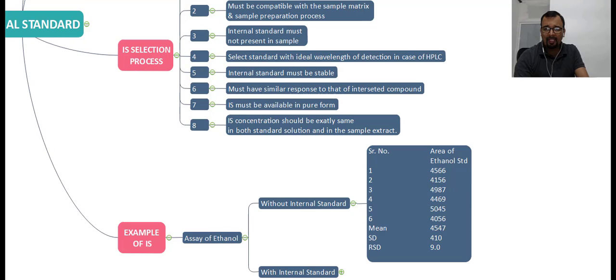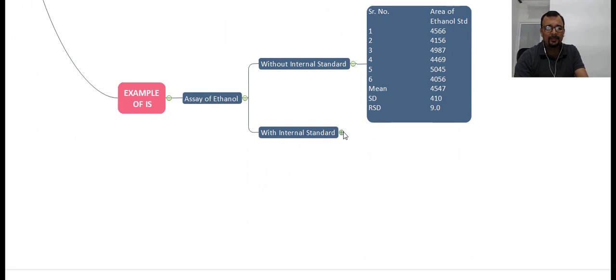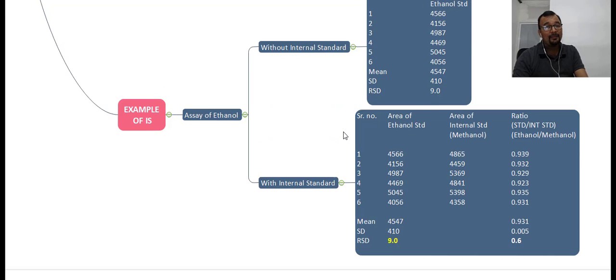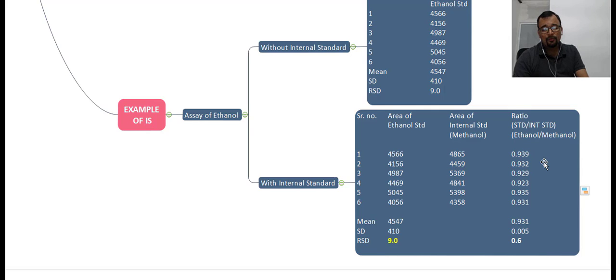Now, in a similar experiment but using an internal standard, methanol is added as the internal standard. Here are the peak responses of the methanol. As part of the process, you calculate the ratio of the ethanol area to the methanol area — for the first injection 0.939, for the second injection 0.932, and similarly for all 6 injections. Calculate the mean of the ratio and the percent RSD comes out to just 0.6%. You can see how the internal standard can help you when you are getting high variability or high percent RSD during system suitability evaluation. Thank you very much for watching, and I will meet you in the next video.